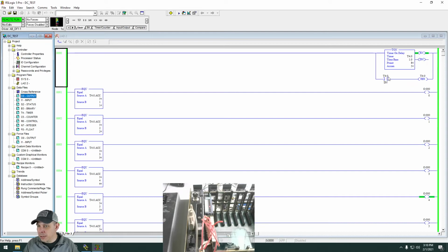So I have that associated with this normally open contact. So as soon as the first scan that it goes through here, so it's scanning these rungs of logic from top to bottom over and over and over really fast. The first scan, it's like a millisecond that it's at 8. So it looks like it never actually counts to 8. So it looks like it only goes to 7, but it's on 7 for a whole second. So that split second that it's on 8, this done bit is actuated, or energized, I should say.